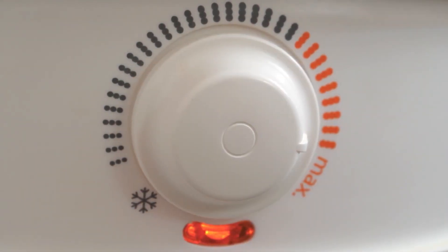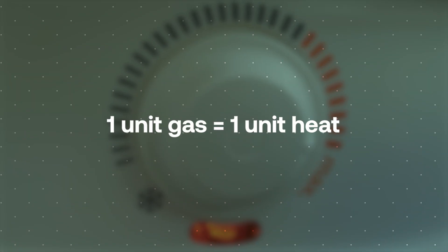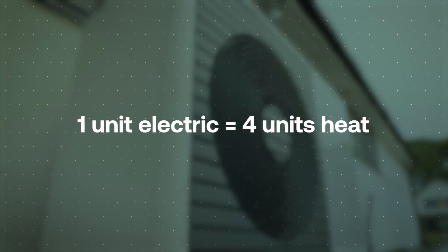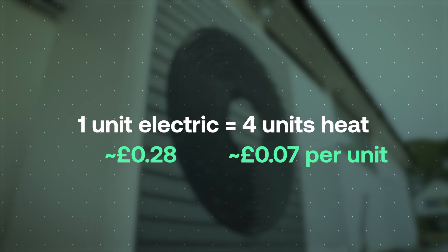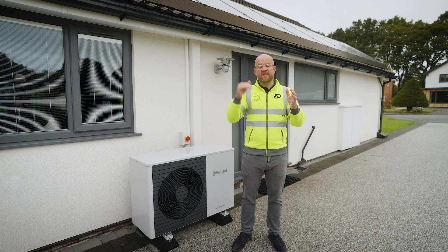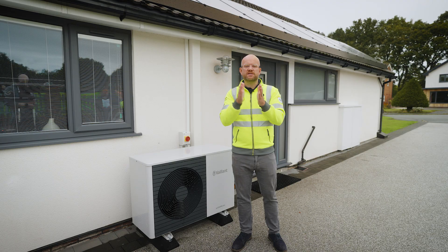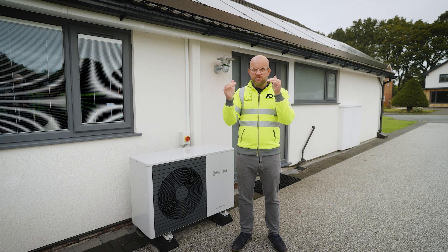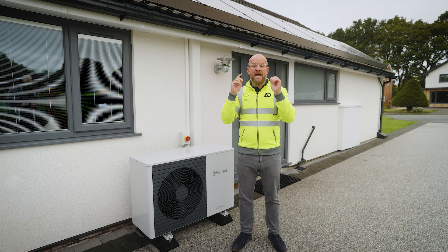Your gas unit price will presently be about six pence, and one unit of gas normally equates to about one unit worth of heat, so a unit of heat costs about six pence. Heat pumps however can turn one unit of electricity into about four or five units worth of heat. The downside is that electricity prices are higher, so often that can work out to a slightly higher bill than gas. If you're cranking the heat pump up to work harder, that efficiency level can drop. Unlike a gas boiler that maintains constant efficiency, the COP — coefficient of performance — rating drops when the temperature drops or if you push the heat pump harder, and this is where the efficiency balance gets misaligned and the price starts skyrocketing.